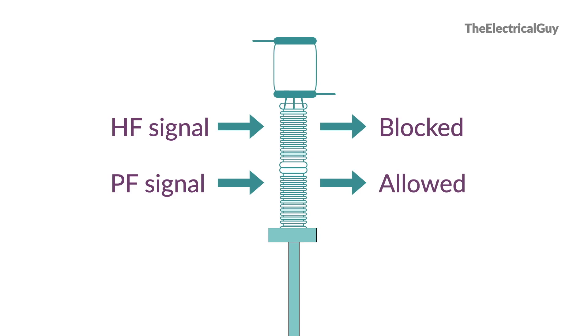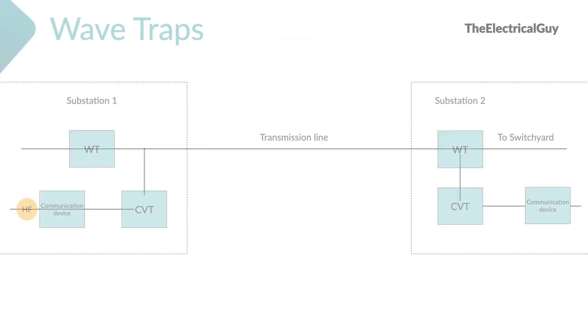They are effectively a low pass filter which has virtually no impedance to power frequency current and a very high impedance to high frequency communication signals.